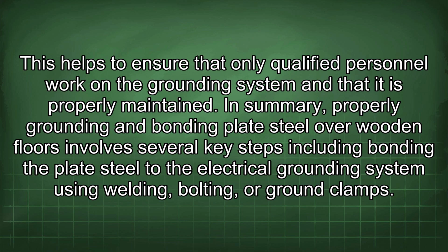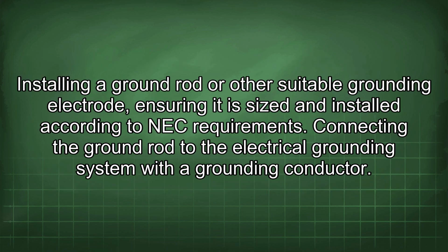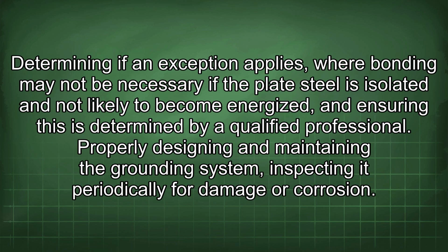In summary, properly grounding and bonding plate steel over wooden floors involves several key steps, including bonding the plate steel to the electrical grounding system using welding, bolting, or ground clamps. Installing a ground rod or other suitable grounding electrode, ensuring it is sized and installed according to NEC requirements. Connecting the ground rod to the electrical grounding system with a grounding conductor. Determining if an exception applies, where bonding may not be necessary if the plate steel is isolated and not likely to become energized, and ensuring this is determined by a qualified professional.